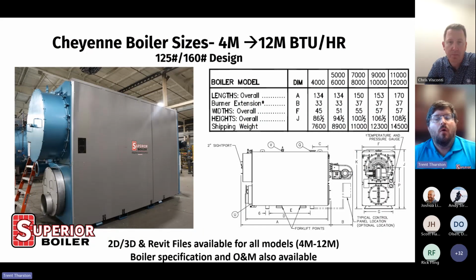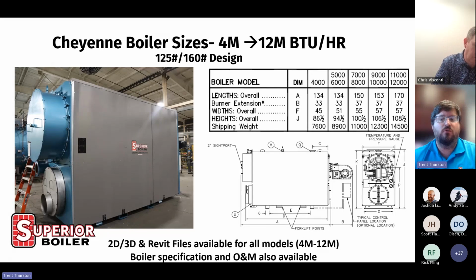So one of the big things with the Cheyenne that separates it is our capacity. We go up to a 12 million BTU input. Our smallest is a 4 million BTU input. One of the biggest things with this is that it allows us to put fewer boilers into a boiler room and still meet capacity. So instead of putting 6 million BTU units in the room, we can put 12 million BTU units in. Again, we have the full range, so if someone does want 6 millions, we can do that. This is a dual fuel high mass condensing boiler, and we're going to touch on how all those affect boiler operation.